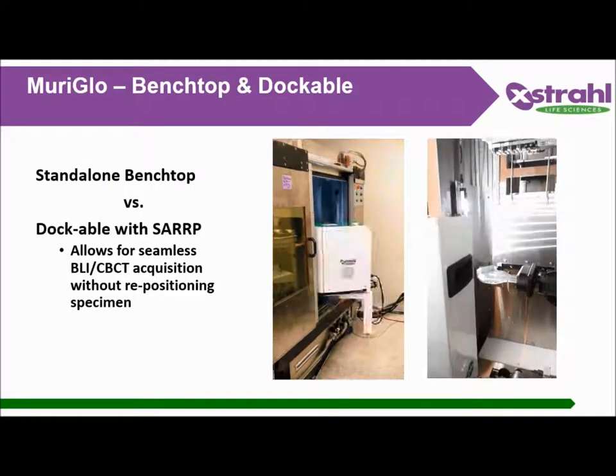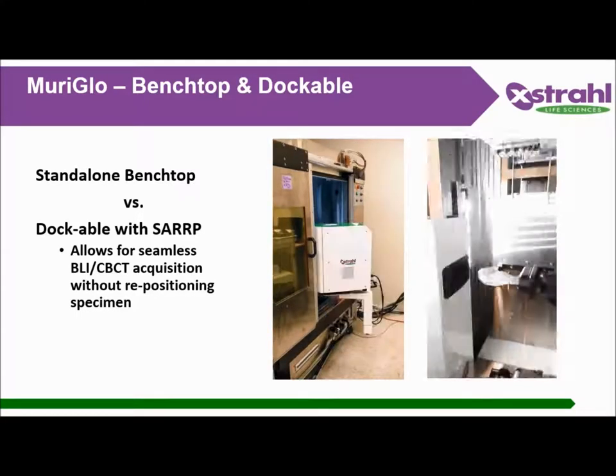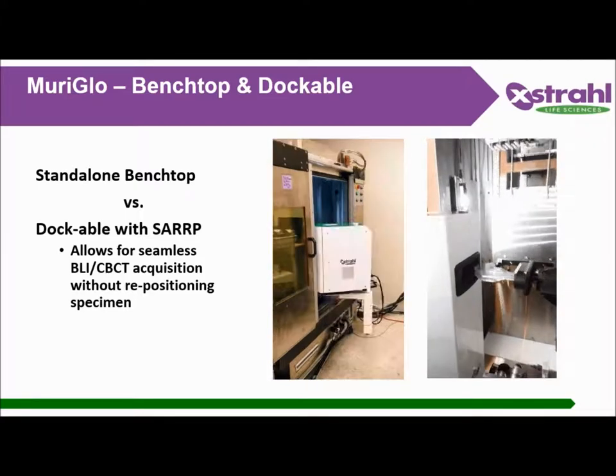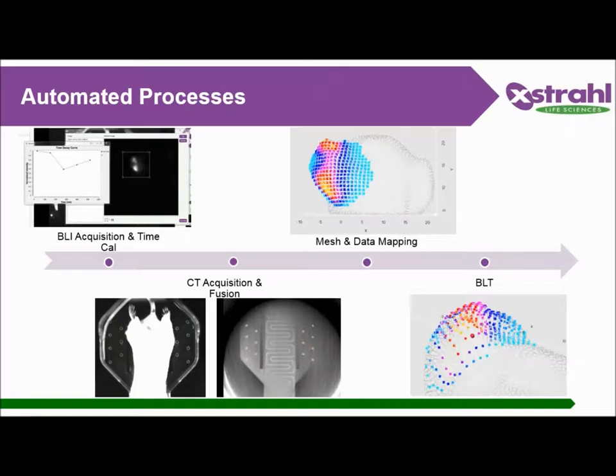This GIF shows the docking process into the SARRP. The bed is used in both the CT and the Muriglo, and there are fiduciary markers on top and bottom for geometry calibration of both the BLI and the CT acquisition. The workflow is: acquire a BLI, calibrate, acquire a CT, fuse, mesh and data mapping, then creation of a center of mass, and you can irradiate.